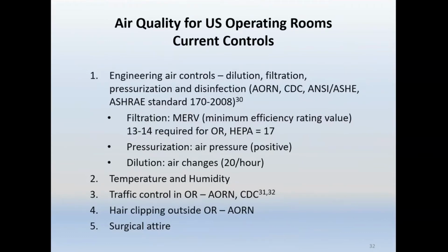The pressure should be positive in the operating room, because we want to prevent organisms from being pulled in toward the case with negative pressure; instead it's pushed out away from the case. Your air needs to be exchanged about 20 times per hour, and you have to check your temperatures and humidities every day to ensure you're within guidelines.